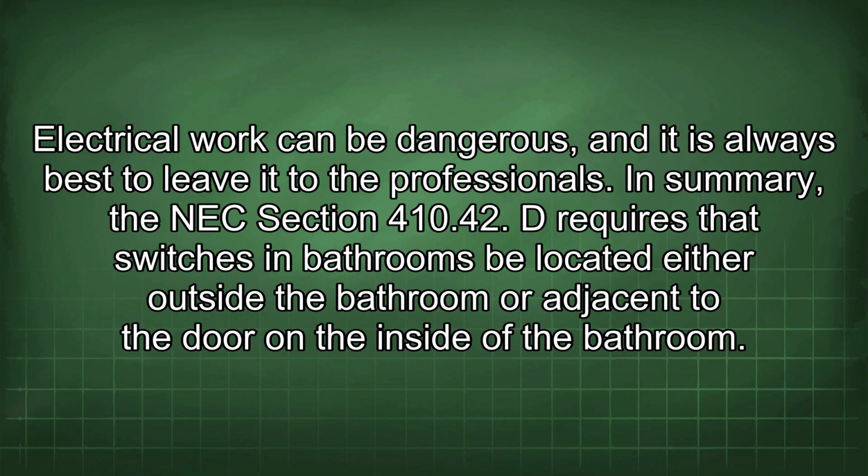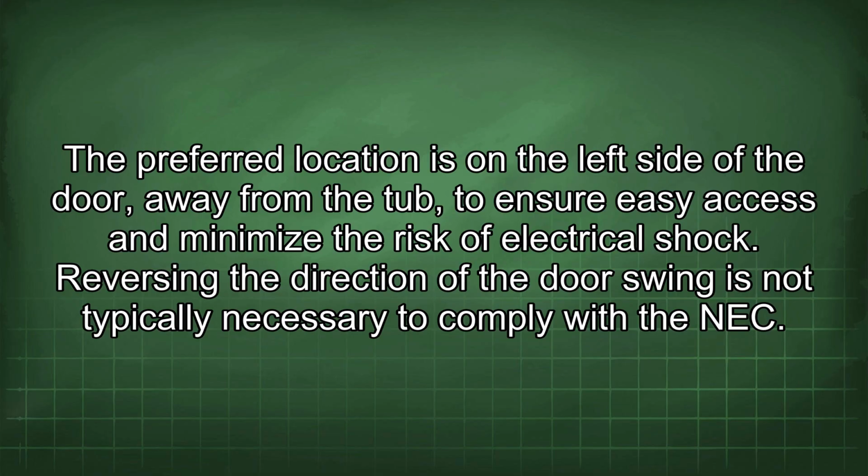In summary, NEC Section 410.42(D) requires that switches in bathrooms be located either outside the bathroom or adjacent to the door on the inside of the bathroom. The preferred location is on the left side of the door, away from the tub, to ensure easy access and minimize the risk of electrical shock.